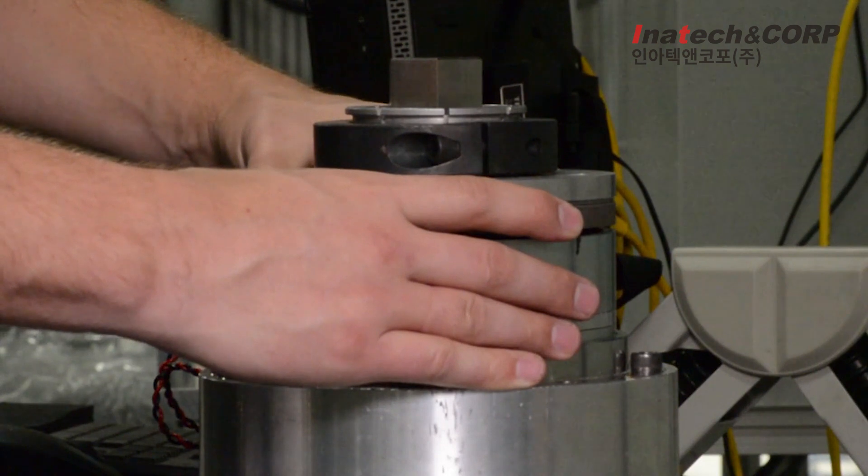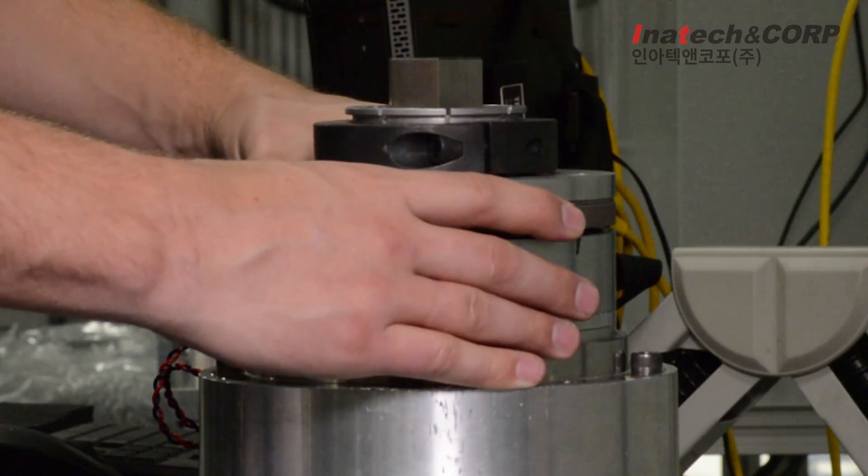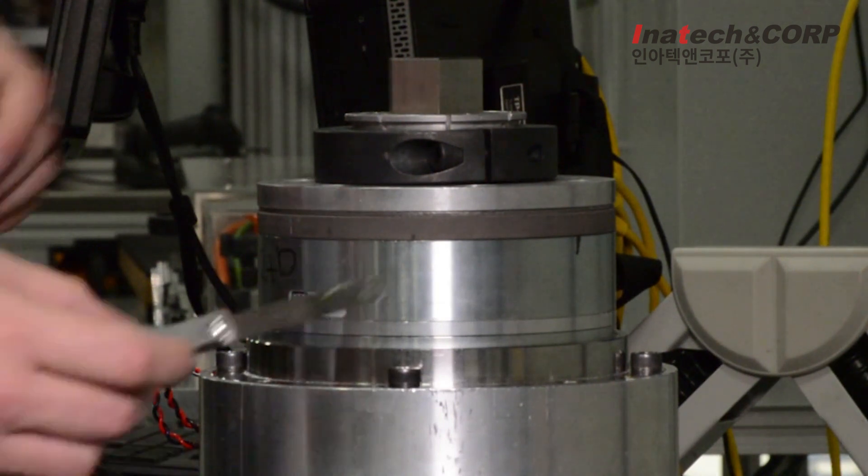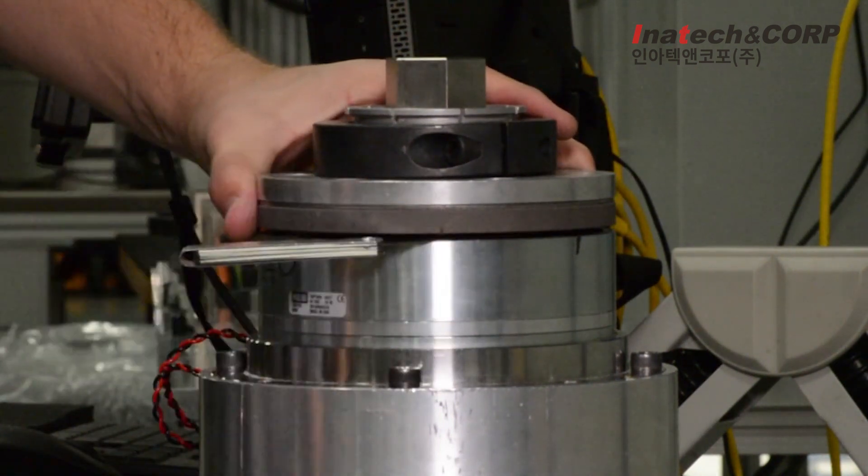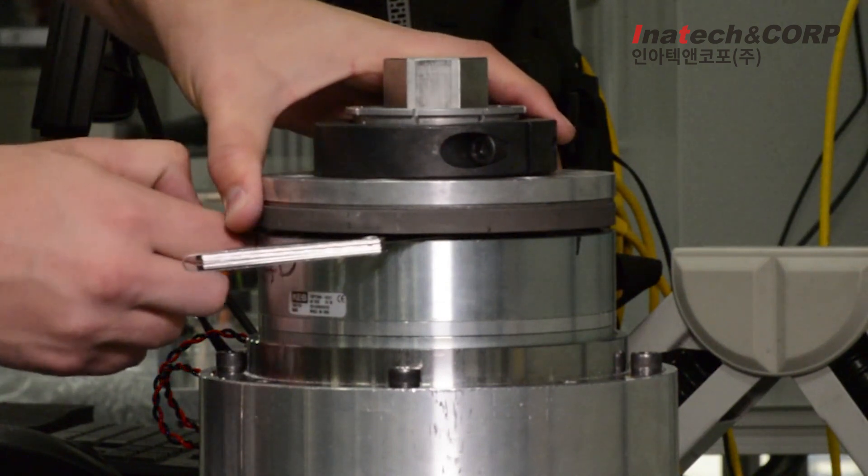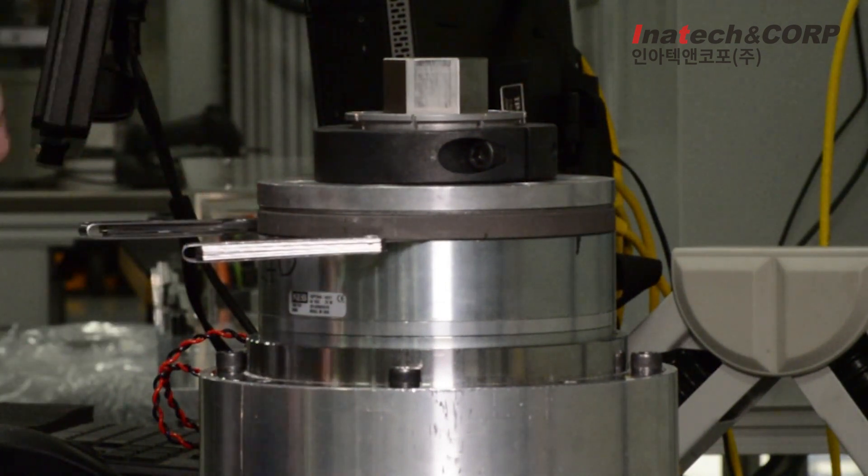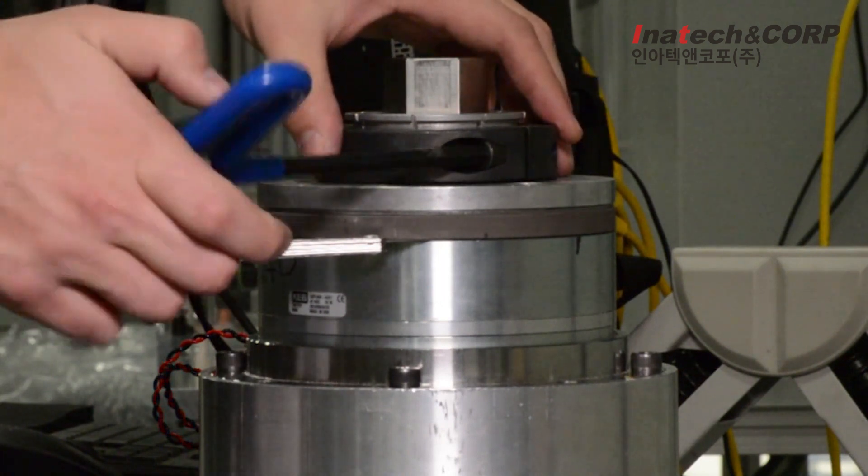Slide the hub armature onto the shaft. Use shims of the proper thickness to set the correct air gap. This brake is a size 10 so the nominal air gap is 0.5 millimeters. When the hub armature is in place at the correct air gap, clamp the collar into place.